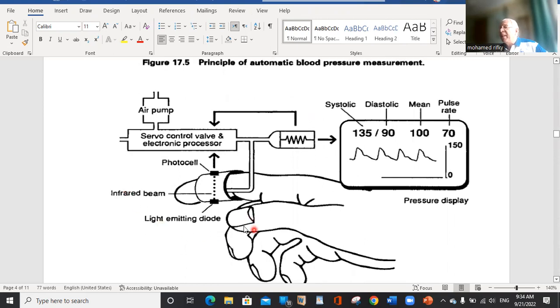And this is the Penaz technique, the Finapres, and this is the photo light emitting diode, and this is the receiving item, where it measures the blood volume of the artery, you see, and it goes to a servo control valve. This servo control valve maintains the photoplethysmography to keep the tracing. You see, it increases to a limit so that it will not compress the artery.